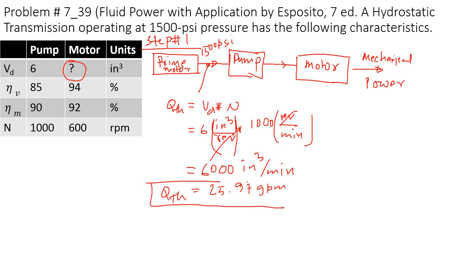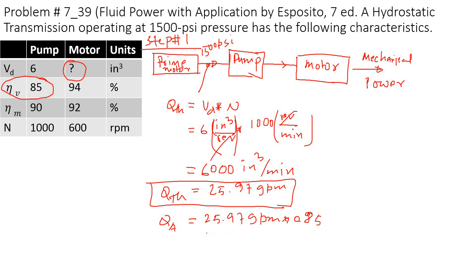In the real world, the pump won't produce that much — the actual flow will be less. The volumetric efficiency is given as 85%, so the actual flow equals 25.97 gpm times 0.85. The actual flow I calculated is 22.1 gallons per minute, or 5100 in³/min.